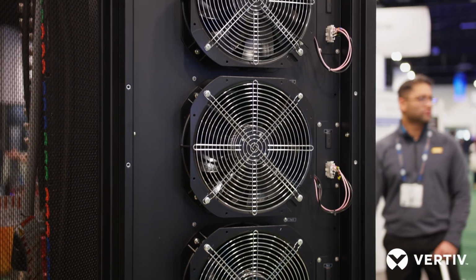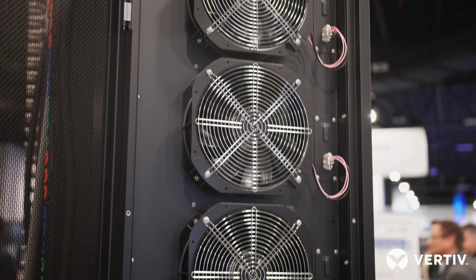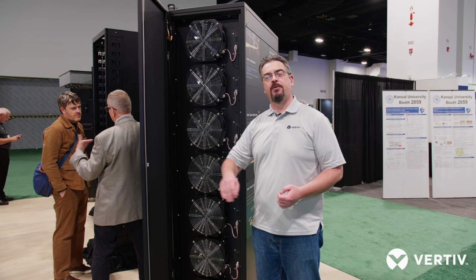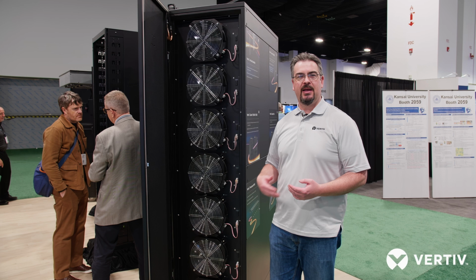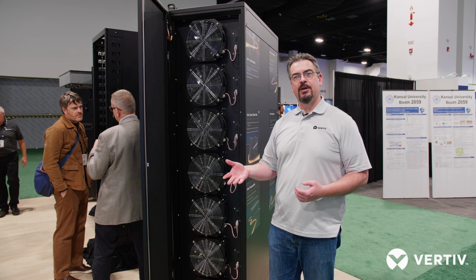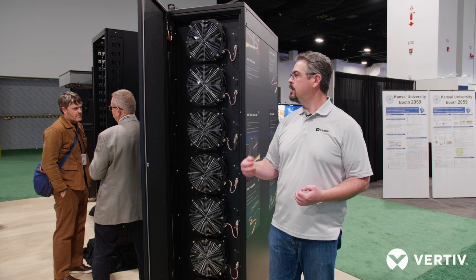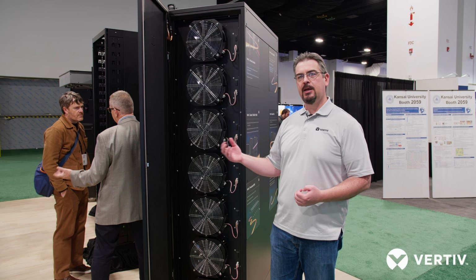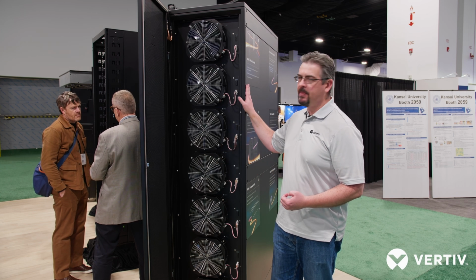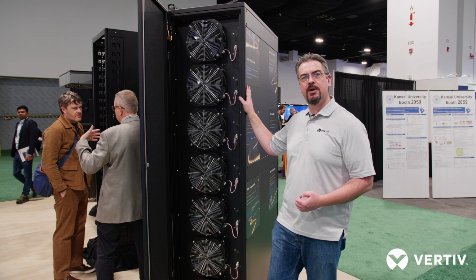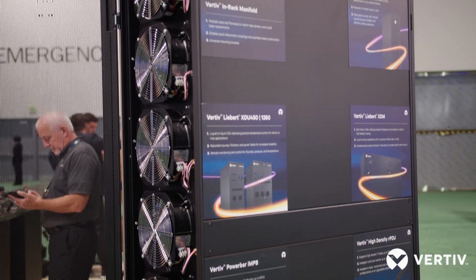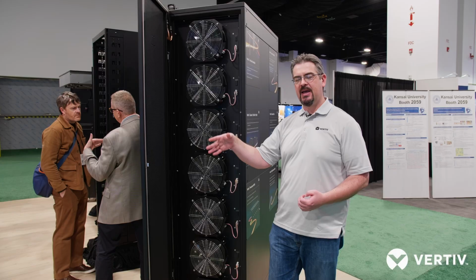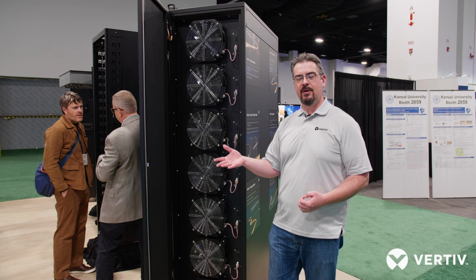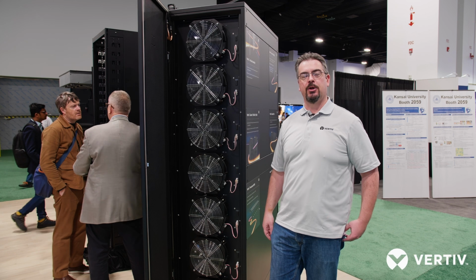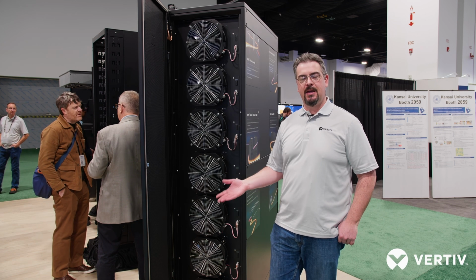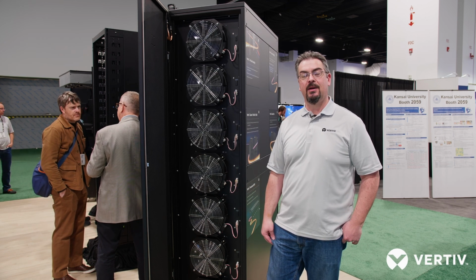Rather than having chilled water plumbed to the unit, we create our own secondary fluid loop between this equipment and the server next to it, supplying that chilled water or coolant water to the chips, to the cold plates, capturing that heat, and then returning it back here and passing it through a liquid-to-air heat exchanger and using fans to exhaust hot air back into the hot aisle, and therefore allowing the customer to use their existing air conditioning equipment to remove that heat and keep operating at an efficient set point.